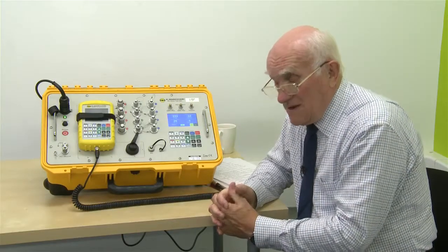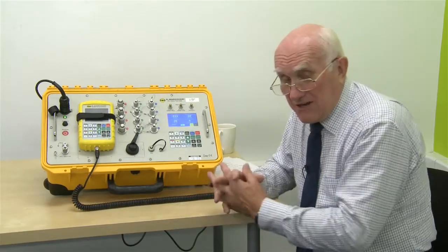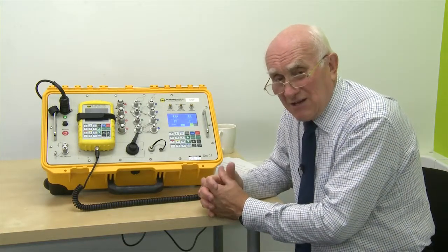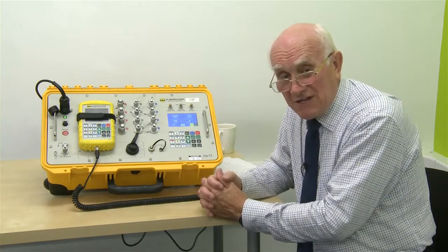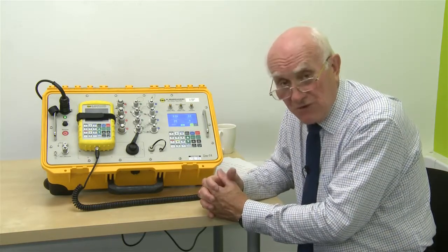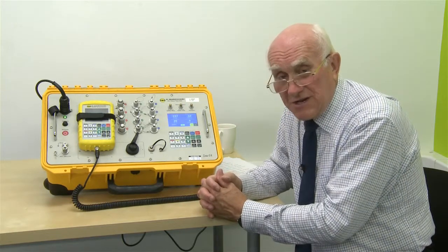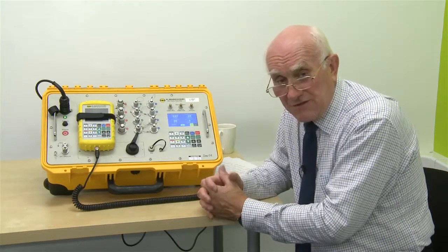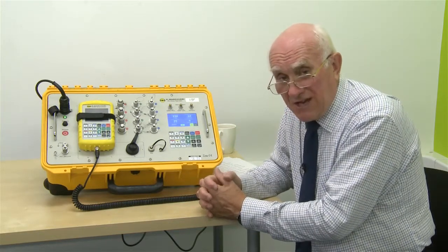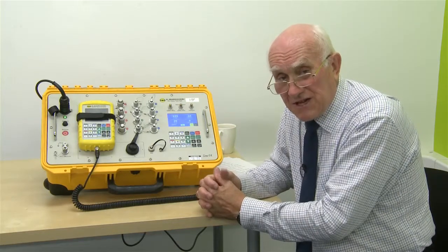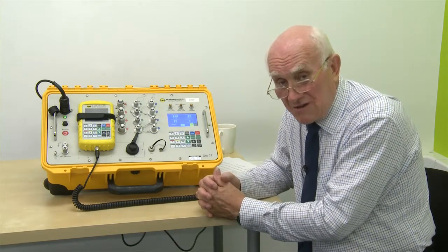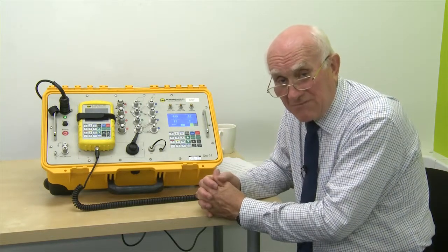In addition, we actually provide another manual, which is the calibration and adjustment manual. This gives you the ability to do calibrations of this instrument, generally speaking on an annual basis, in your own premises through your own calibration laboratories, if you so wish. However, if you would like to return it to ourselves, we will happily give you that service on a 1-year basis. Only remember that if you're going to do the calibrations yourself, it must be against first-class reference standards. There is the joke that if you compare it against a piece of string, you'll get a piece of string. You won't have a decent calibration.